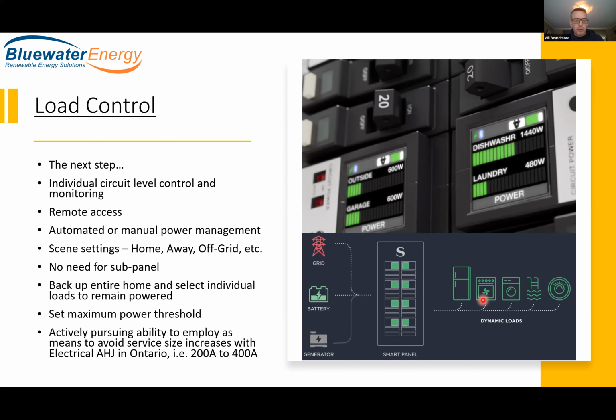When there's a grid outage, we can automatically shed certain loads if we have a limited amount of backup power - such as right now, as I discussed earlier, we're limited to a maximum of 3 Powerwalls, giving us a maximum of 15 kilowatts of backup power. We see loads in homes getting over 15 kilowatts if everything were to come on. So this system can be programmed so that larger non-essential loads are shed and don't receive power in a grid outage situation.